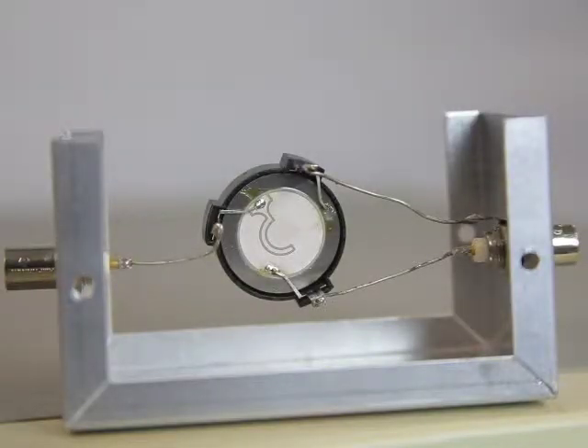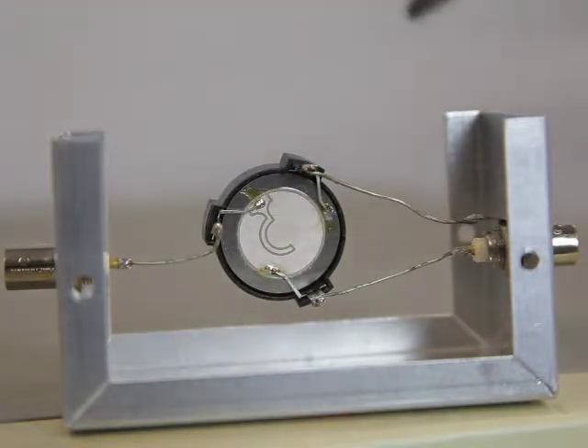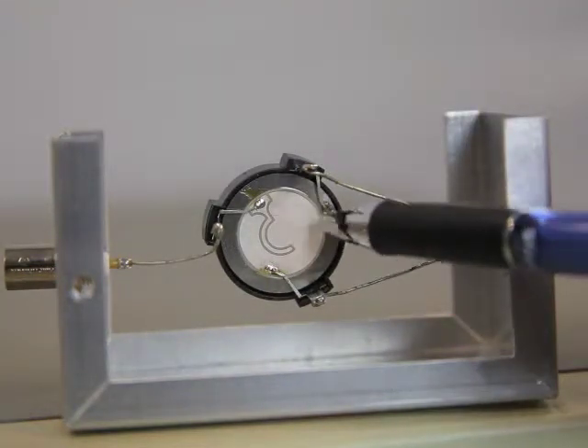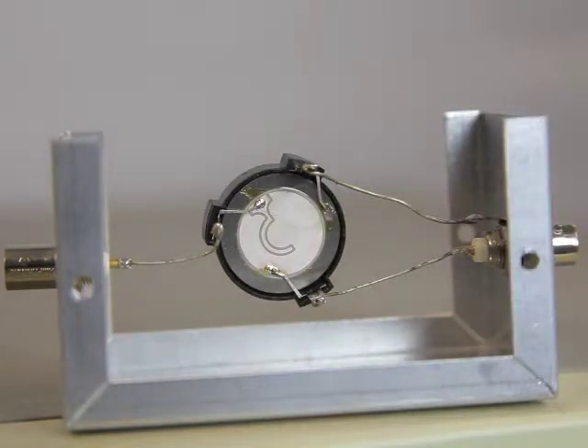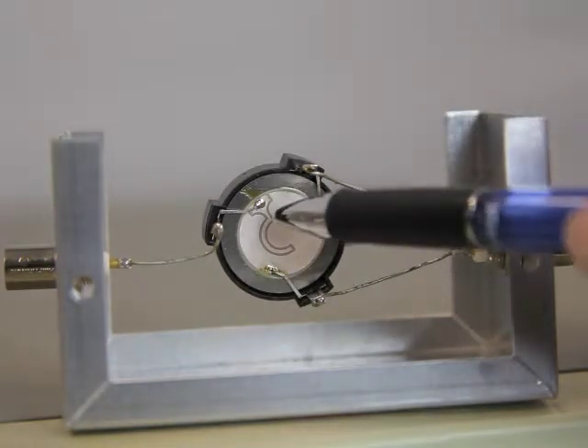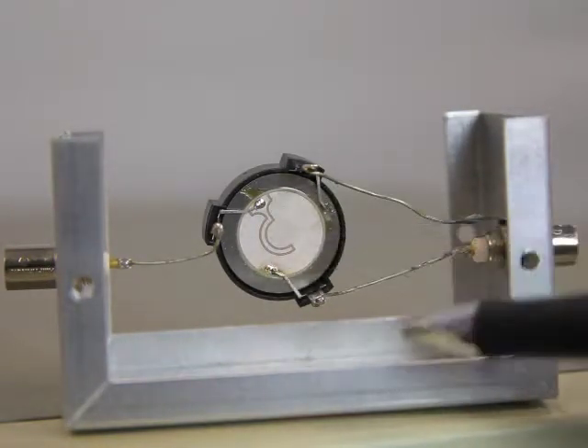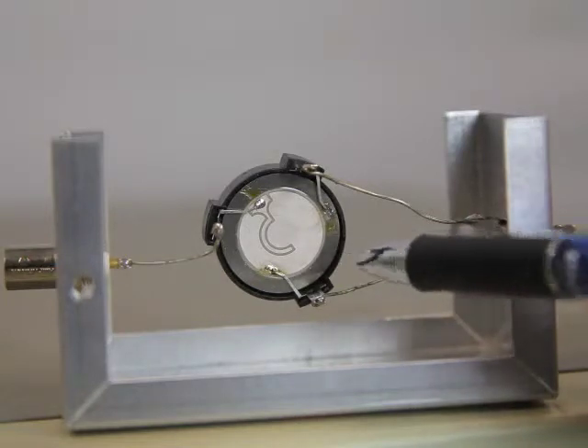This is the piezo ceramic flexural disk that you will be measuring. There are three connections on it. There's the drive, which is the larger area here. There's the sensing element, which is the center part here. And then there's the ground, which is the outer part.